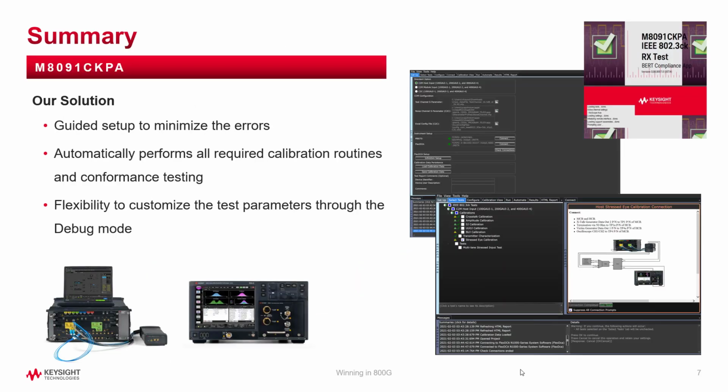In summary, the app provides the value in reducing both the errors and user interaction to a minimum by performing all the required calibration routines and conformance testing automatically that comply with 802.3ck standard. Besides, you have the flexibility to go beyond the standard and customize the test parameters through the debug mode.